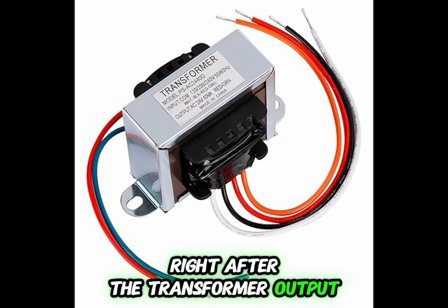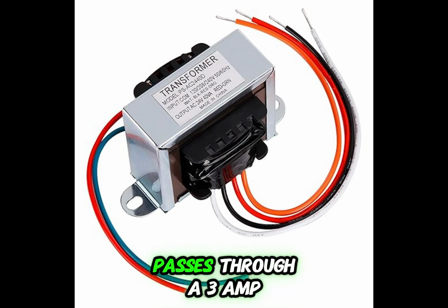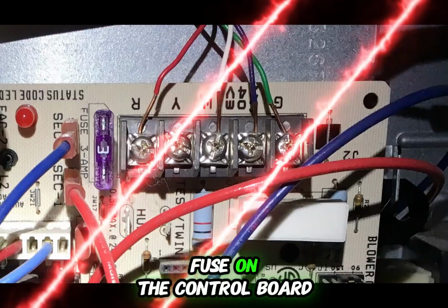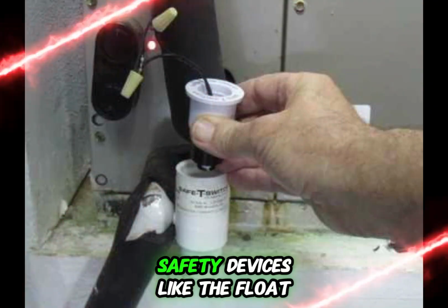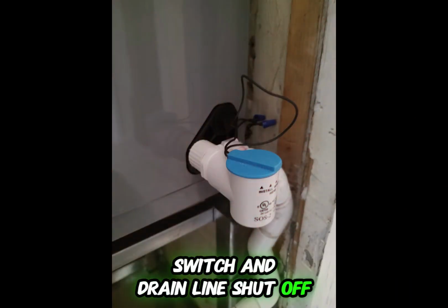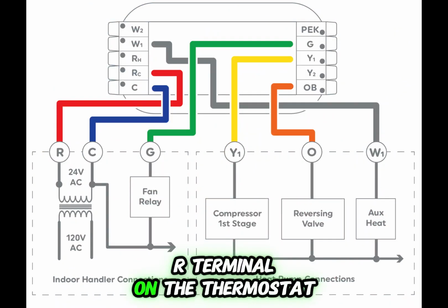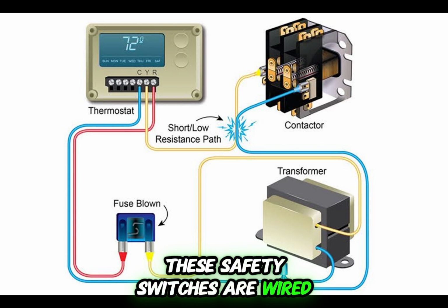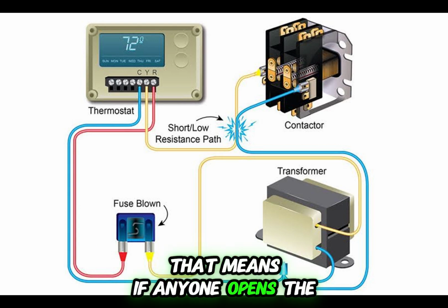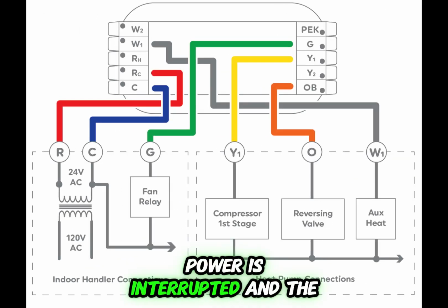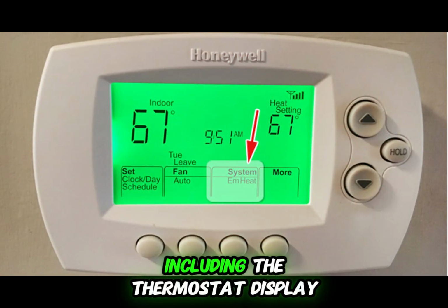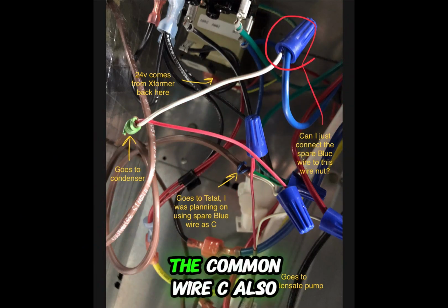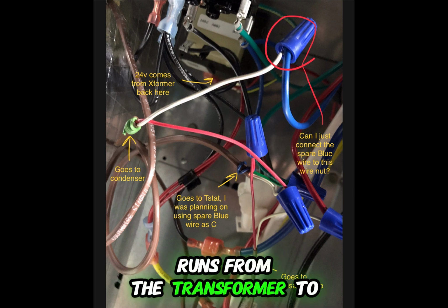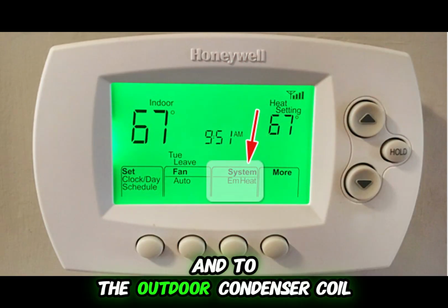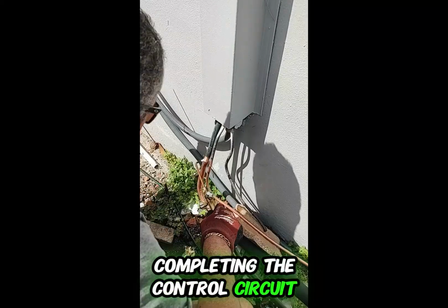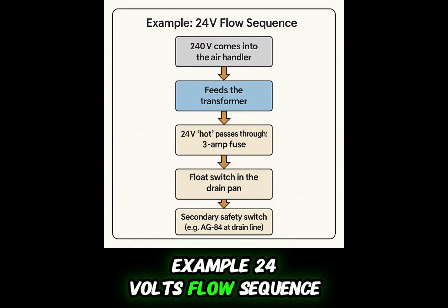Right after the transformer output, the 24-volt hot wire passes through a 3-amp fuse on the control board, if present. Then safety devices like the float switch and drain line shut off. Then it connects to the R terminal on the thermostat. These safety switches are wired in series. That means if any one opens, the 24-volt power is interrupted and the whole system shuts down, including the thermostat display. The common wire C also runs from the transformer to the thermostat and to the outdoor condenser coil, completing the control circuit.